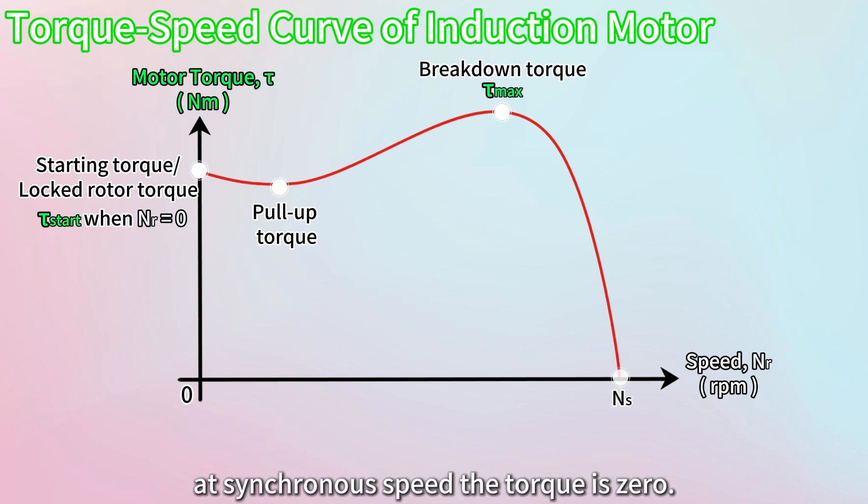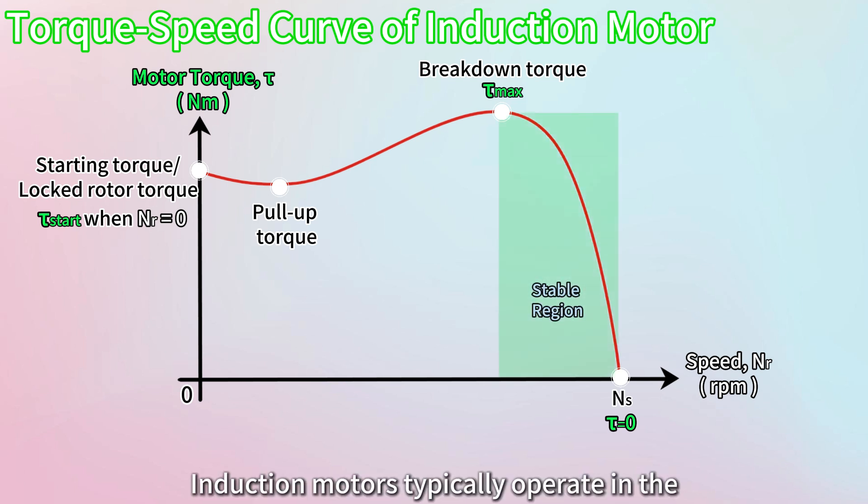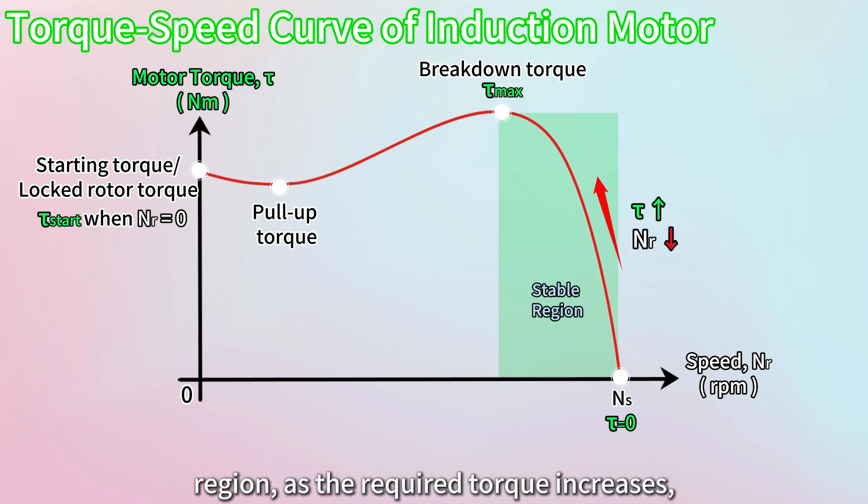Lastly, as you might have guessed at synchronous speed, the torque is zero. Induction motors typically operate in the stable region of the torque speed curve, which is located to the right. In this region, as the required torque increases, the motor speed will gradually decrease, maintaining stable and efficient operation under varying loads.